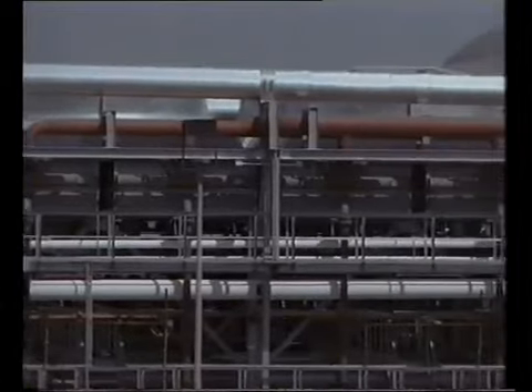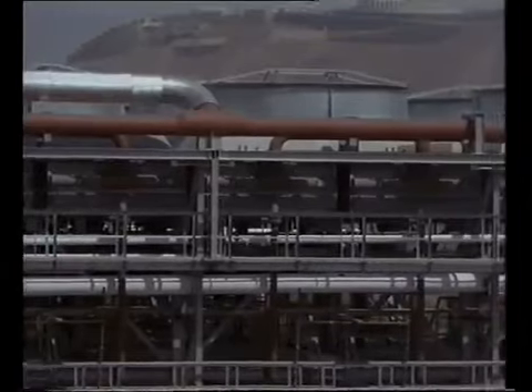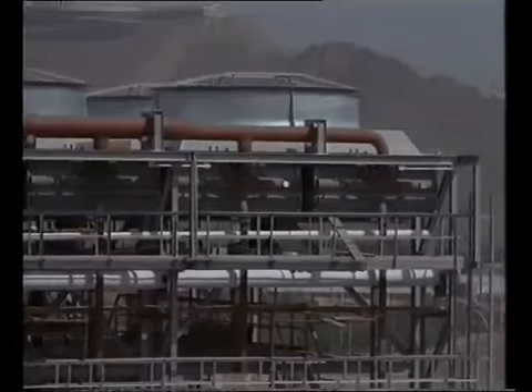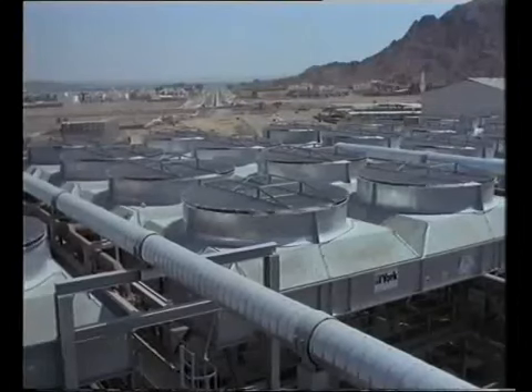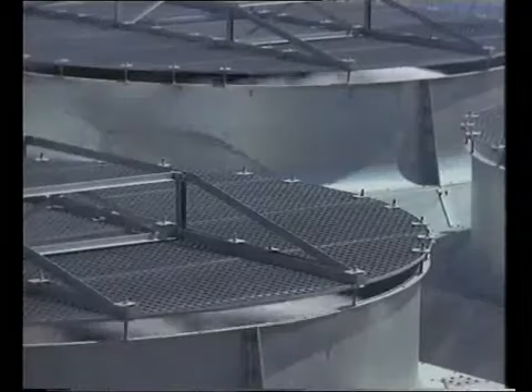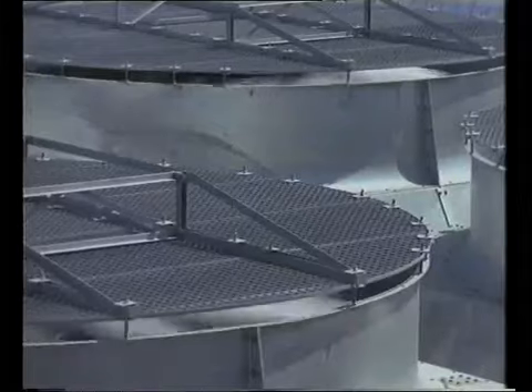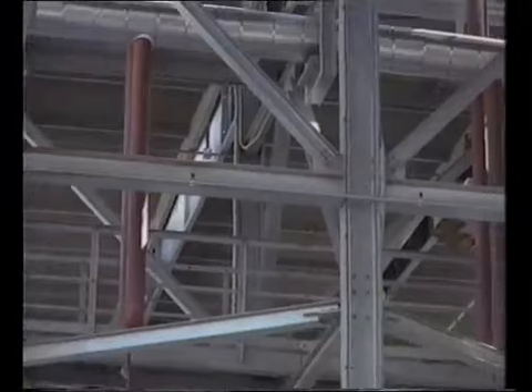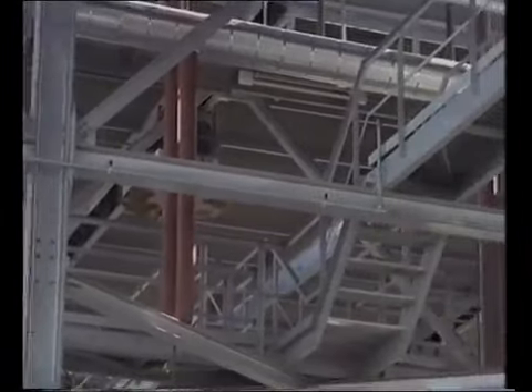Each one has a surface area of 360 square meters, making this rig the largest air cooling condenser system in the world. 8 fans draw up air around the refrigerant as it passes below, through 3 layers of narrow gauge tubing. The fans turn at 200 revs per minute, and the updraft of air is enough to lower the temperature of the refrigerant to 50 degrees centigrade, just above the ambient air temperature. This causes the gas to lose its heat. By the time it reaches the bottom layer of tubing, the refrigerant has turned back into its liquid form.